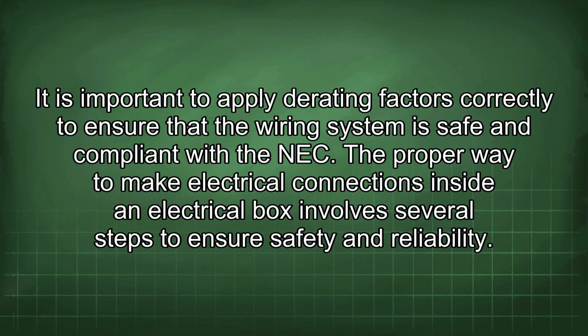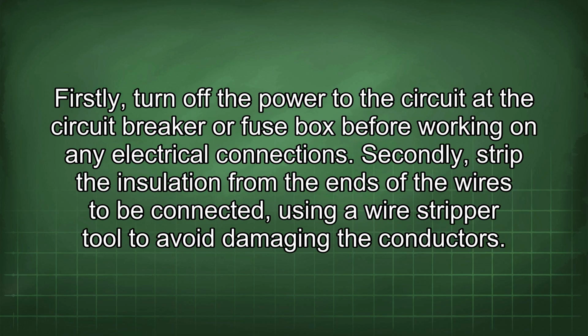The proper way to make electrical connections inside an electrical box involves several steps to ensure safety and reliability. Firstly, turn off the power to the circuit at the circuit breaker or fuse box before working on any electrical connections. Secondly, strip the insulation from the ends of the wires to be connected, using a wire stripper tool to avoid damaging the conductors.